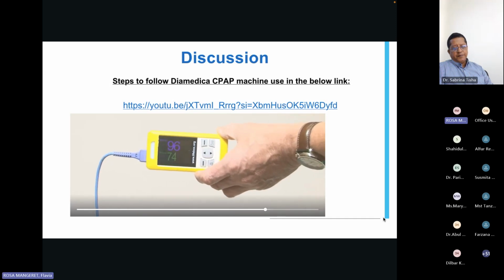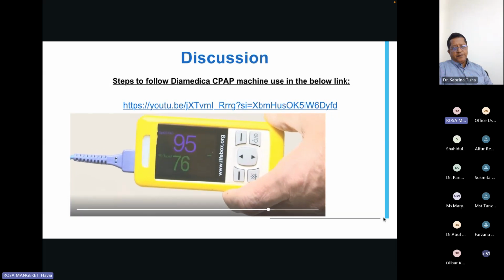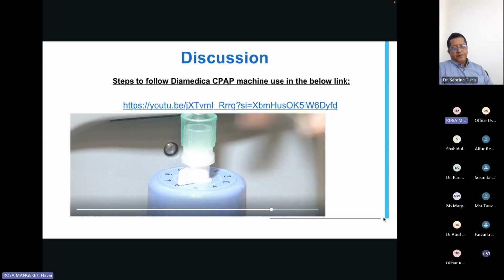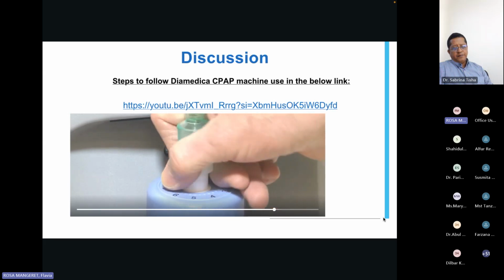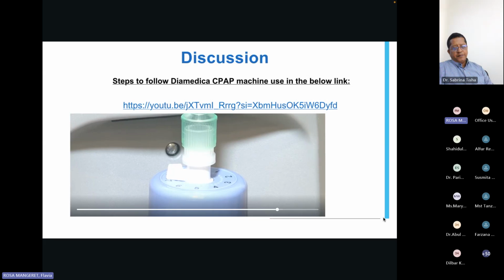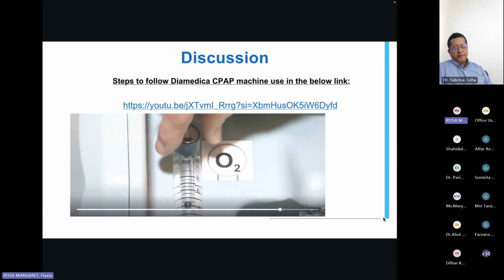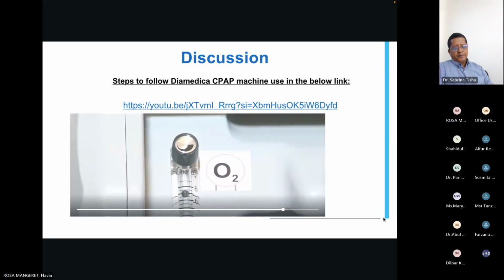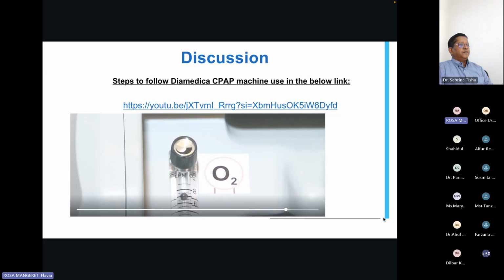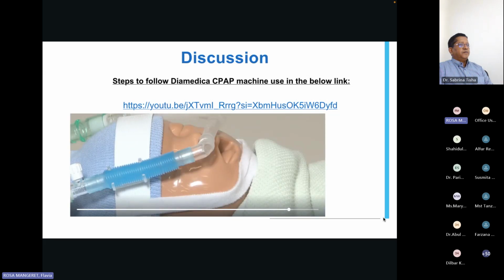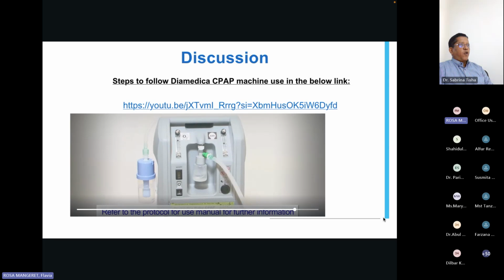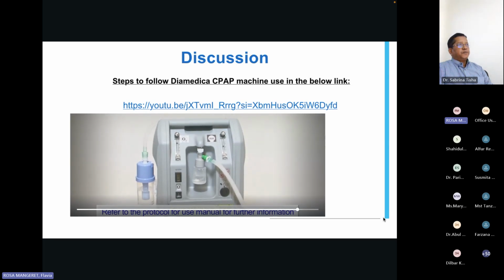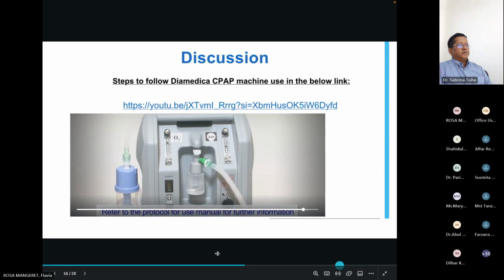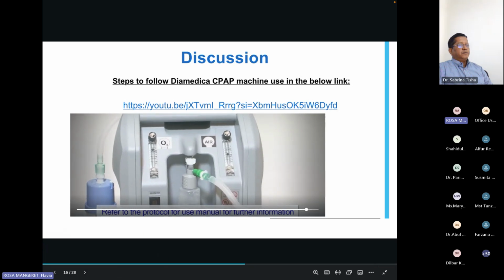If the level of oxygen saturation is below 90%, or the child has severe respiratory distress, first increase the CPAP level to 8 or 10 centimeters of water, and then, if no response, increase the oxygen flow meter to as much as 8 litres a minute. If there are still no continuous bubbles, check the nasal prongs are attached properly and reposition them so they fit snugly inside the nostrils. If there are still no continuous bubbles, check for leaks along the circuit and adjust the oxygen or air flows according to the chart in the manual. Refer to the Protocol for Use manual for further information.